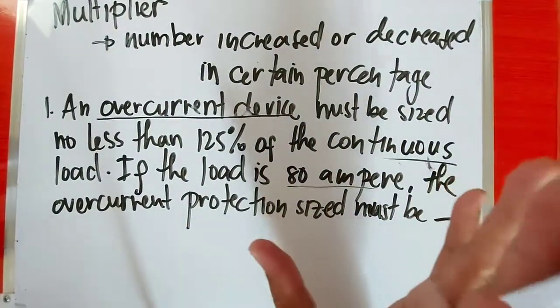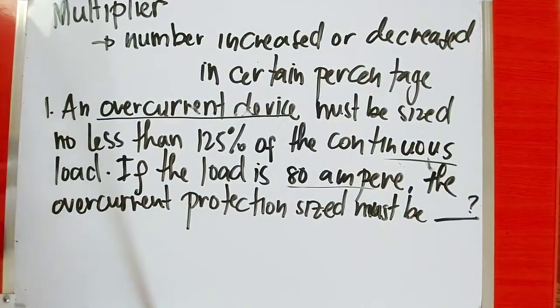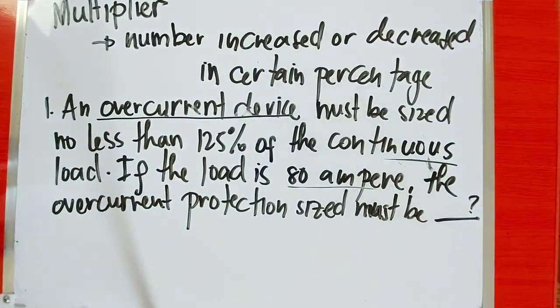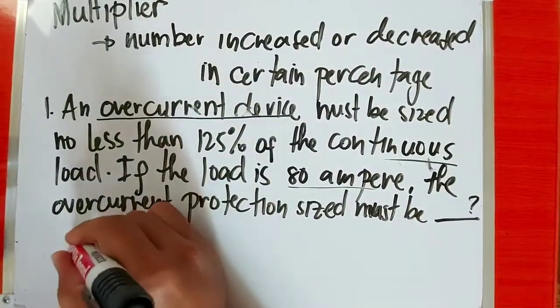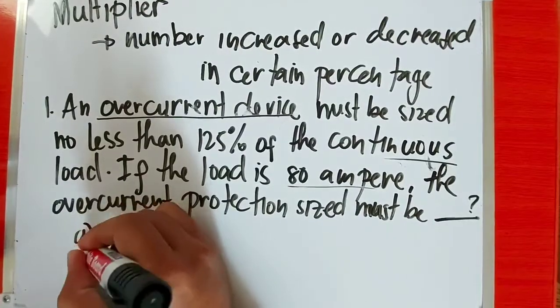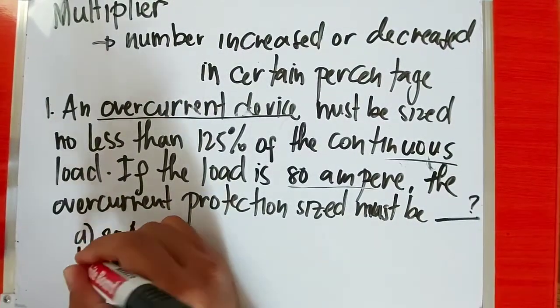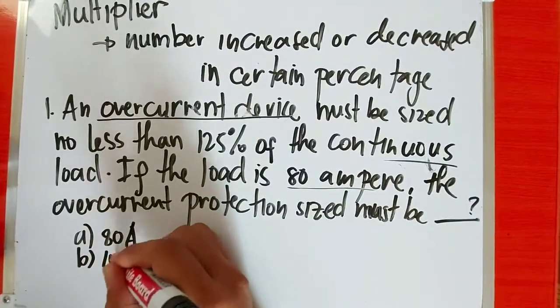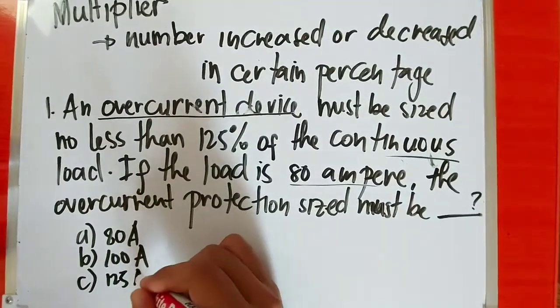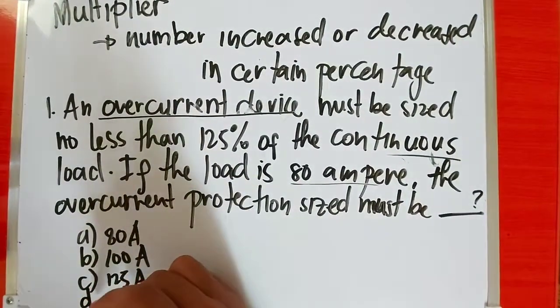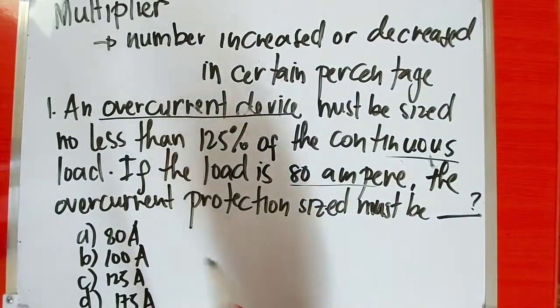So, overcurrent protective device - this is the circuit breaker or fuse. You need to size it at 125% if it's a continuous load. So whatever the load is, you multiply it by 125%. So if there are choices, for example: letter A is 80A, letter B is 100A, letter C is 125A, and letter D is 175A. So these are the choices.